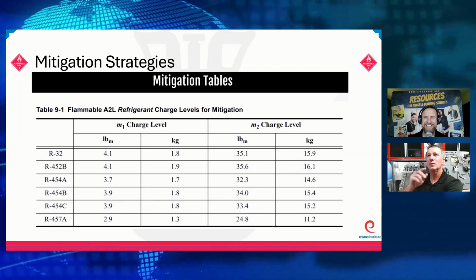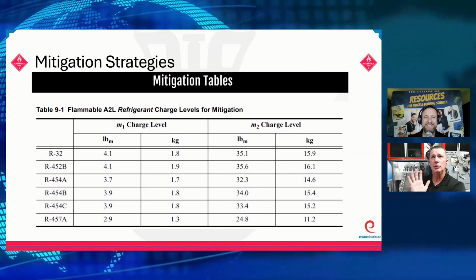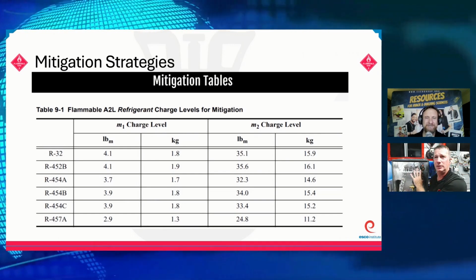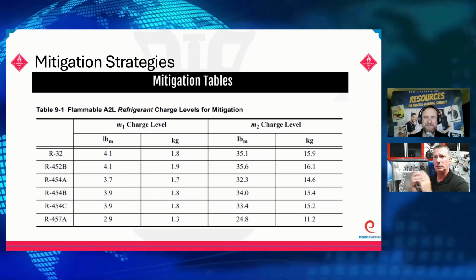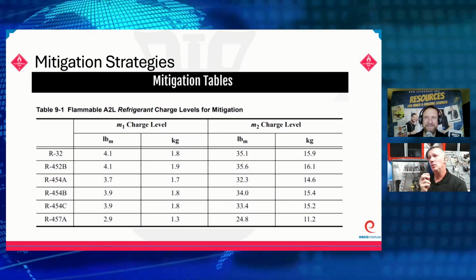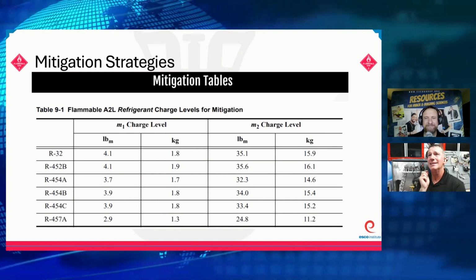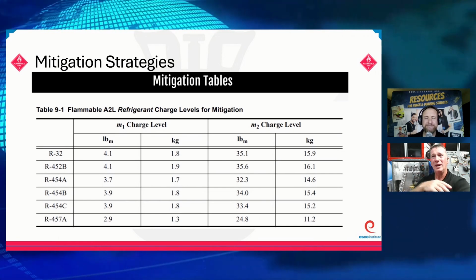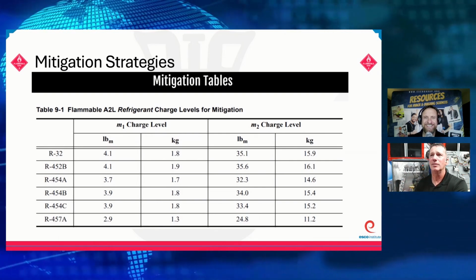Okay. So on this particular unit, let's take this new installation and assume for a moment that this is a complete new system installation. This is my R32 indoor cased coil with its refrigerant detection sensor. We have our R32 condensing unit or heat pump outside. We have a new gas furnace, but it hasn't been updated to the newest version of control board that has the mitigation sequence built into it. What would I need to do to have a sequence of mitigation with that? Let's think about that for a minute.